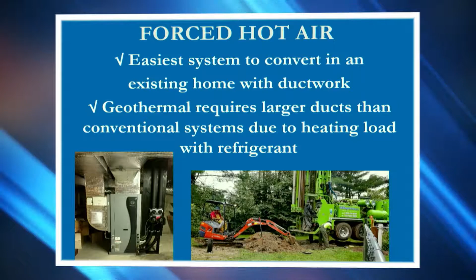We can do baseboard, but usually you need double the square footage of wall space because the highest temperature that you really want to run geothermal efficiently is around 120 degrees. Most baseboard in your homes now operate at around 180 degrees to get 580 BTUs per foot. To do it with forced hot water, we'd have to put a different type of baseboard in, which will give you higher temperature with lower water temp incoming. The issue is usually you have to double the square footage of baseboard.